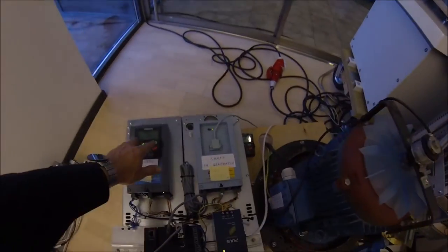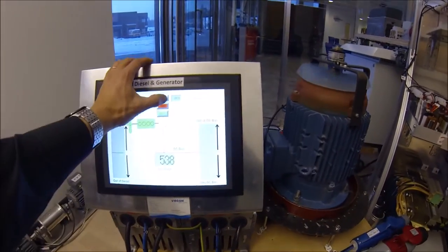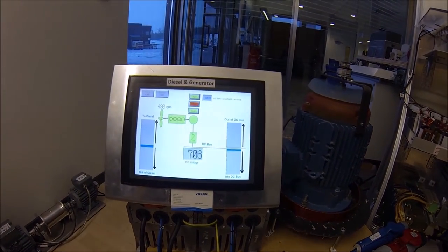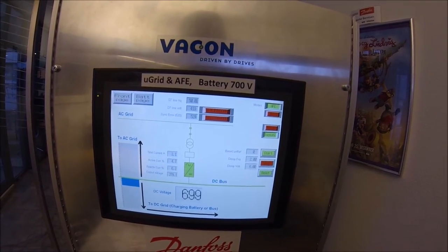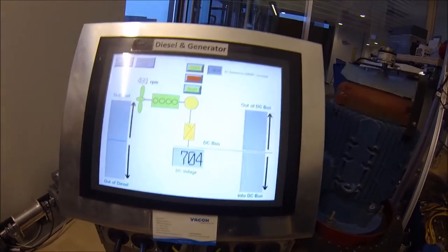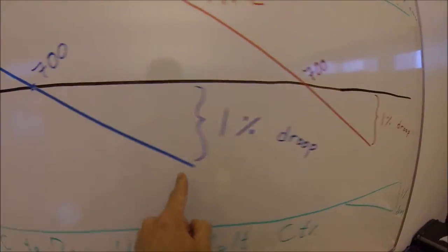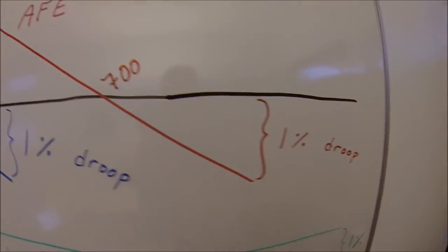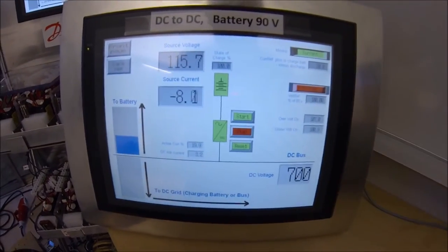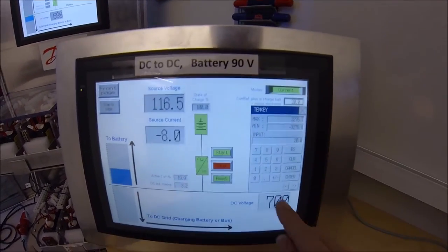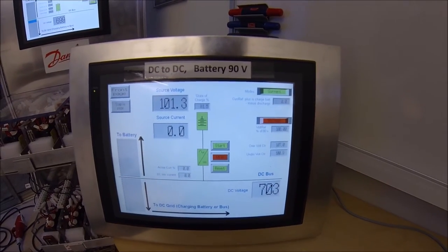Let's start the diesel engine — if I produce energy from here it's 700 volts. I also have the possibility with a grid converter to produce 700 volts, taking power from the city. These two can work together because they have been calibrated to the same nominal and the same drooping. Nominal 700 and a one percent drooping. We also have a DC-to-DC converter in the same system which has been set up to work nicely in a 700 volt nominal environment.